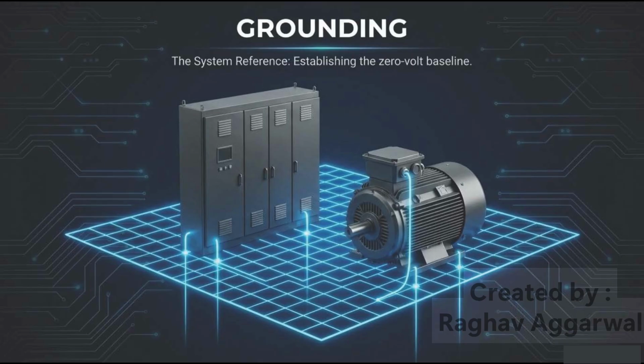We now move from safety protection to system performance. Let's study the concept of grounding now. Grounding is described as the system reference that establishes a 0-volt baseline. In practical terms, all electrical measurements and operations require a common reference point. Without a stable reference, equipment may not operate predictably. Measurements may become inaccurate, and system behavior can become unstable. Grounding helps electrical systems maintain consistency across generators, equipment, and connected devices. By tying components to a common ground reference, engineers create a more predictable operating environment.